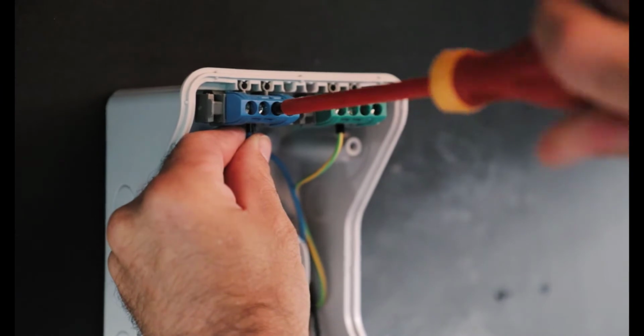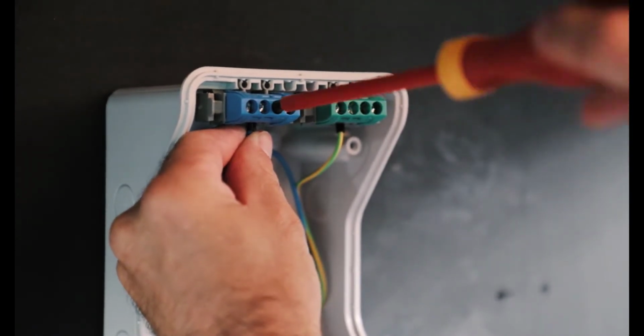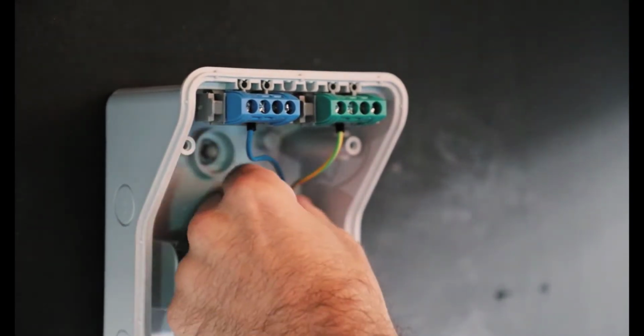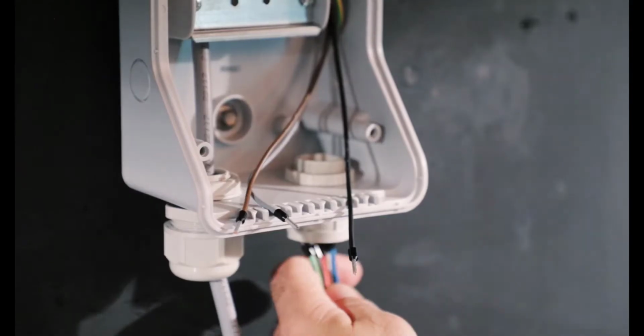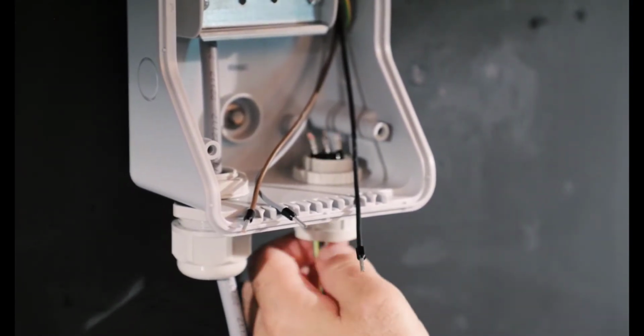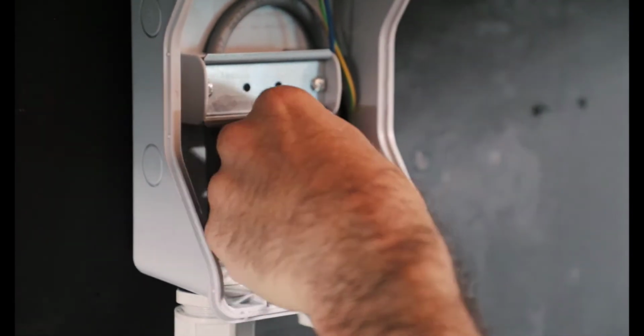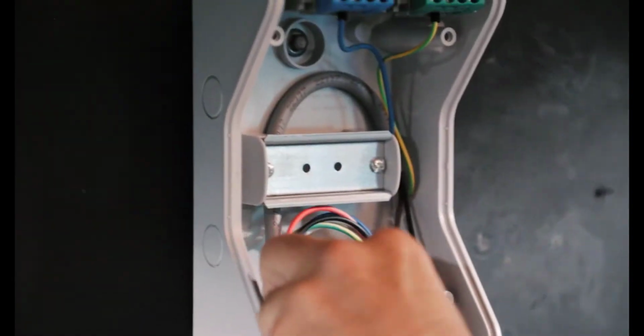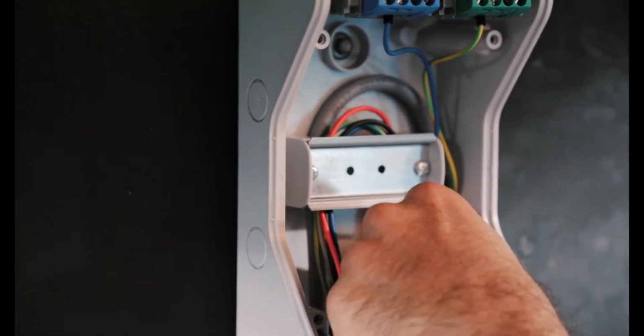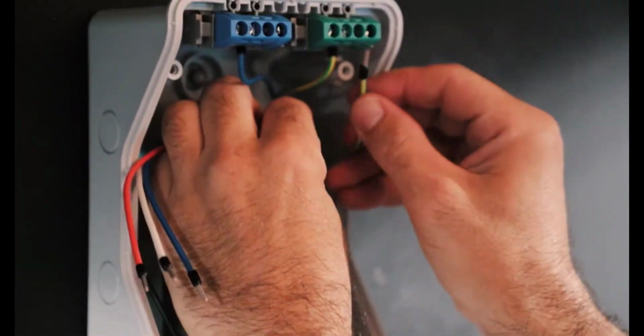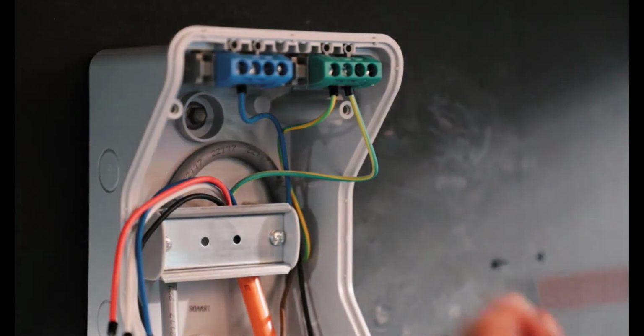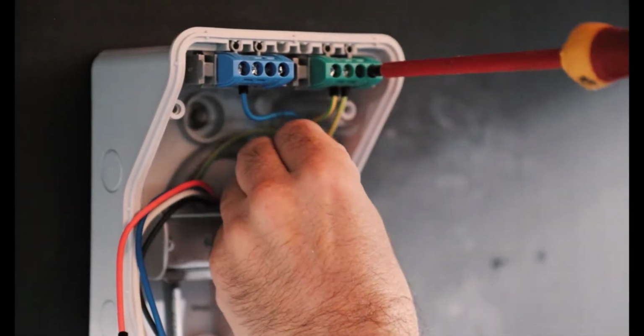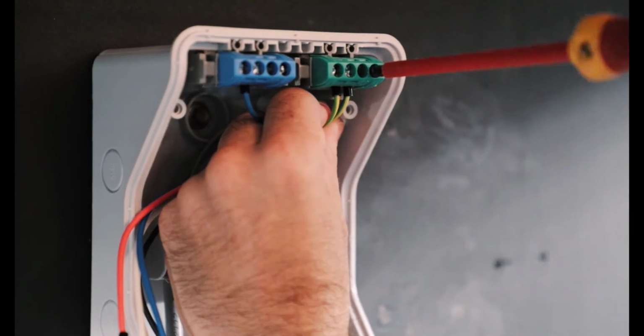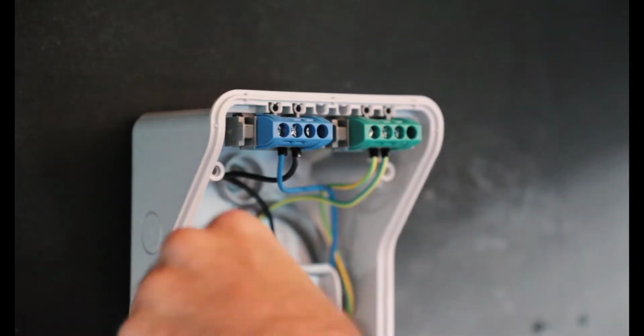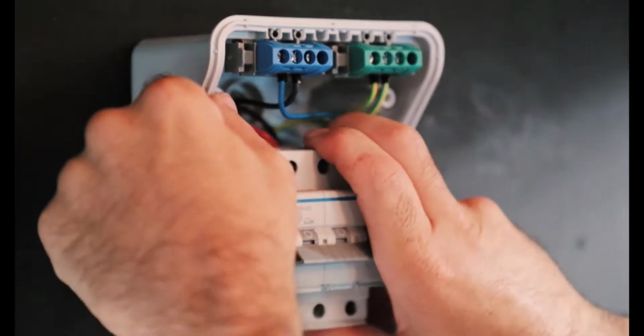Now, as these Sonnen systems cater for all different situations, we can't be specific on isolation requirements and cable run requirements and everything else, so we don't supply the isolators for the Sonnen systems. The recommendation here is that an isolator, probably up to about 20 amps, is sufficient. The 8.03 has a charge discharge capability of 3.3 kilowatts, so 1.1 per phase. Now, this obviously needs to be a latched isolator to be able to break all of the poles simultaneously.